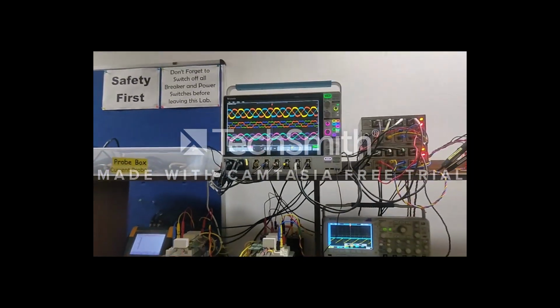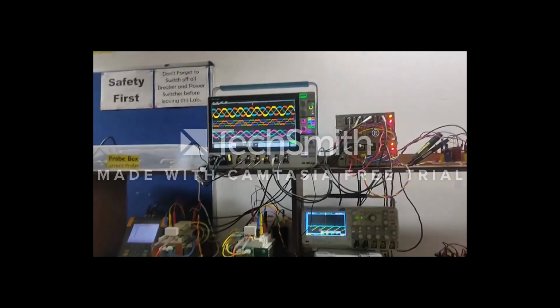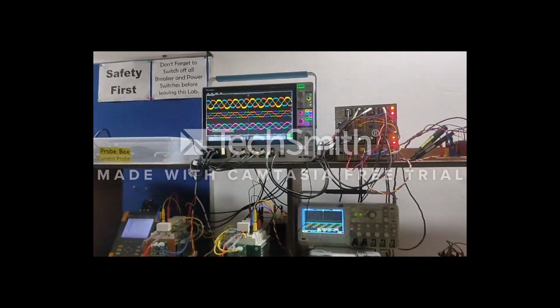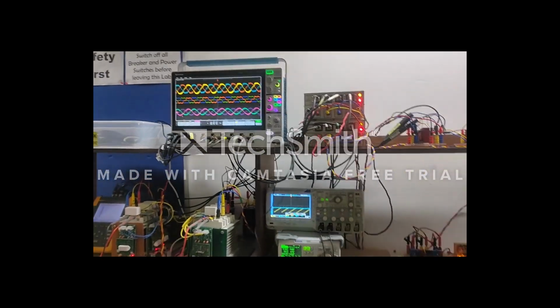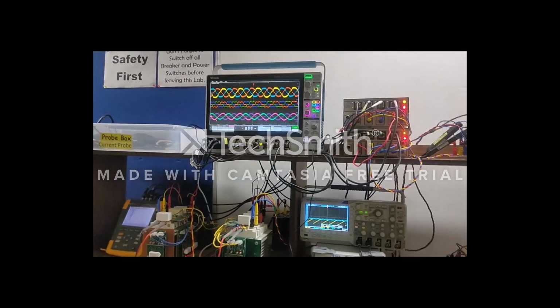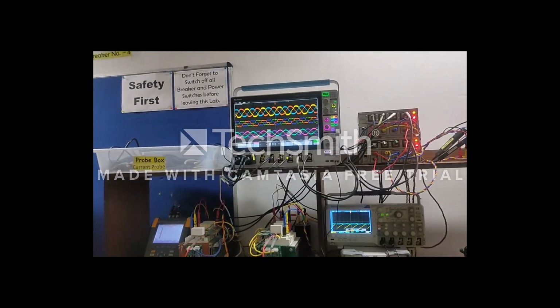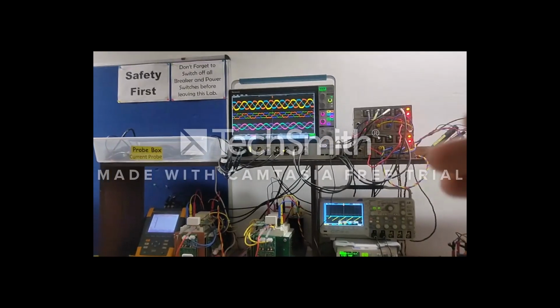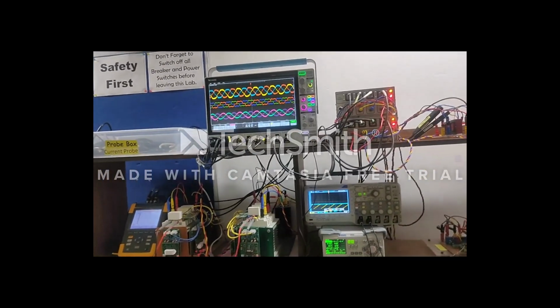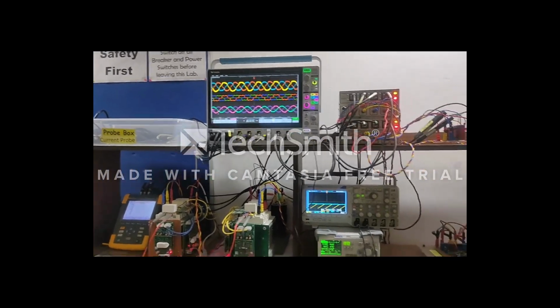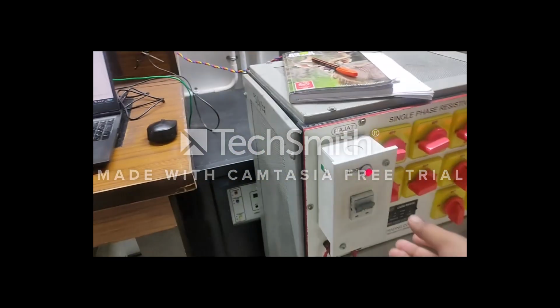So this is the mode 1 operation. In mode 2 operation there is no non-linear load presented, which means the non-linear load current is totally 0. So whatever the available power at the source is directly injected into the grid. Because there is no non-linear load, there is no need for harmonic compensation. So now we are turning on the non-linear load.